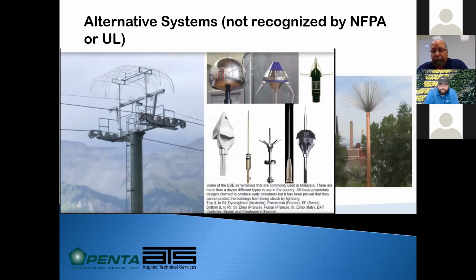Great. And then there's one additional question from Jason. Stephen, do you have any stories or experience with a scenario where the lightning protection system does its job on the roof, but then fails somewhere inside the building before it gets to the ground? I guess it's kind of hard to say. If it did its job on the roof, it wouldn't really get into the building. But that being said, we do have several clients that have been struck and received no damage inside the building and no damage on the top side.